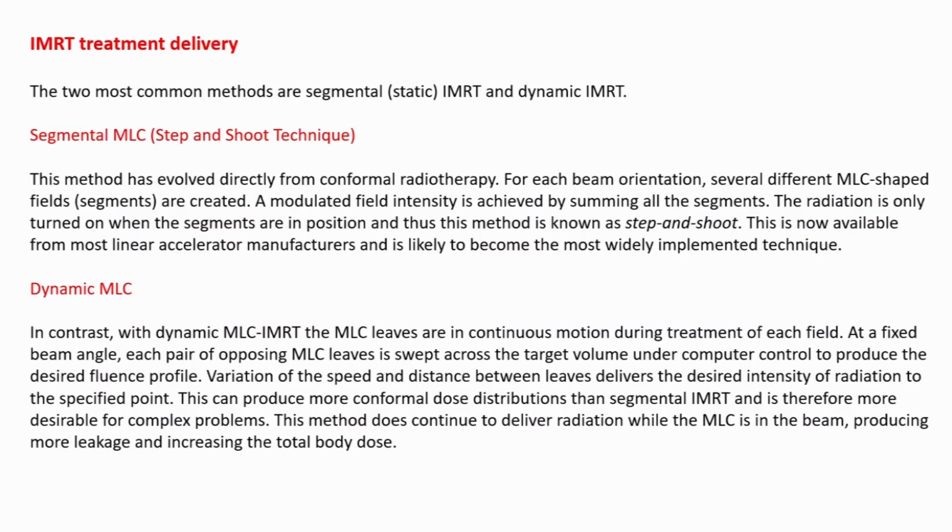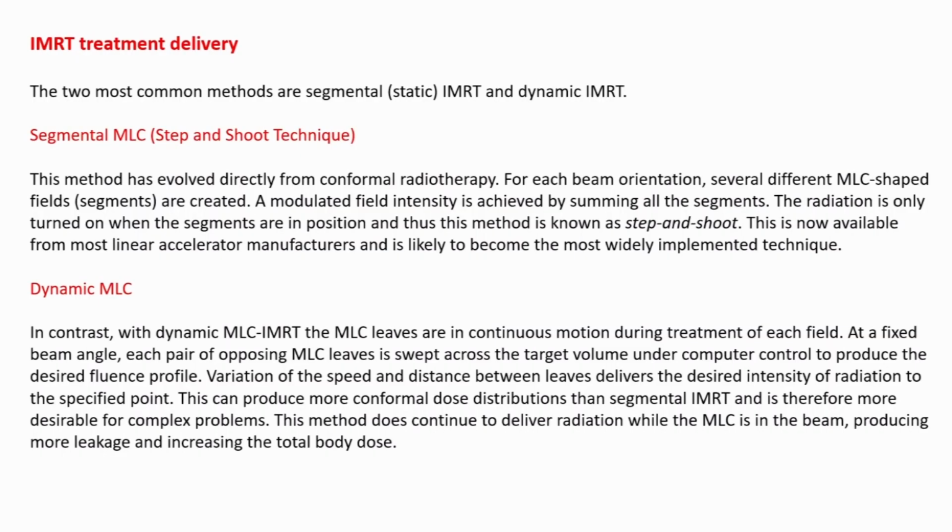So in short, in the step and shoot delivery technique, the multi-leaf collimator forms a segment, taking the shape of a segment beam. Once the MLC takes the shape of a segment, the beam is on, and on going to the next segment, the beam is off.